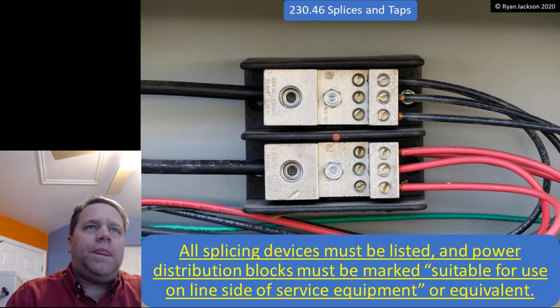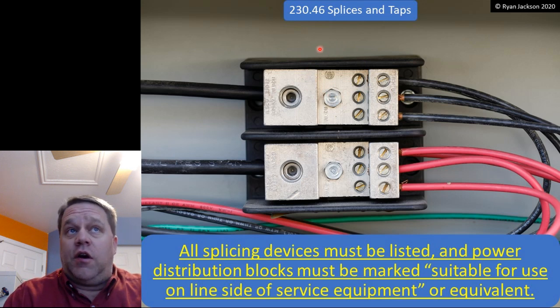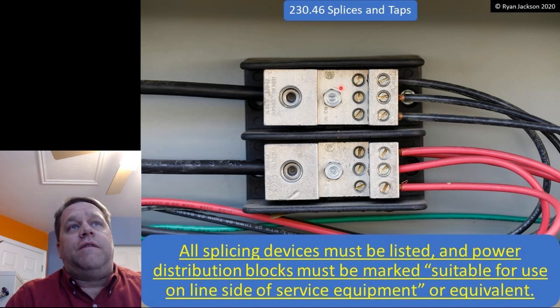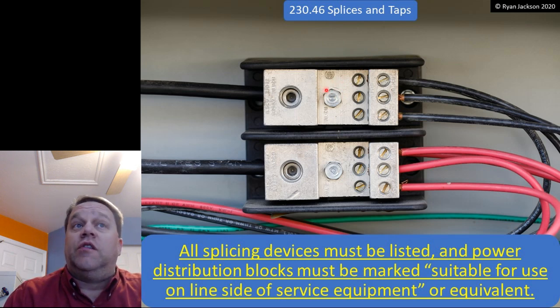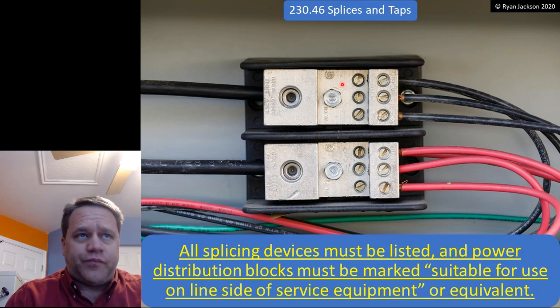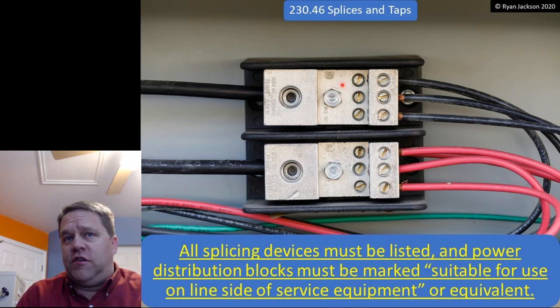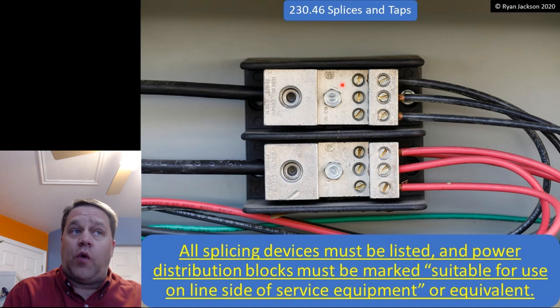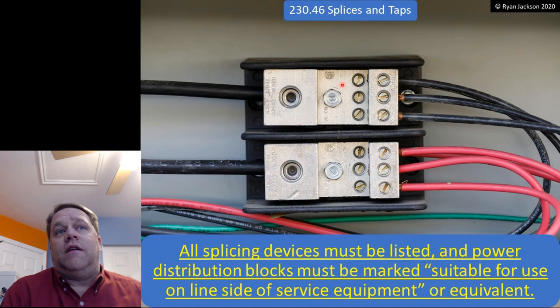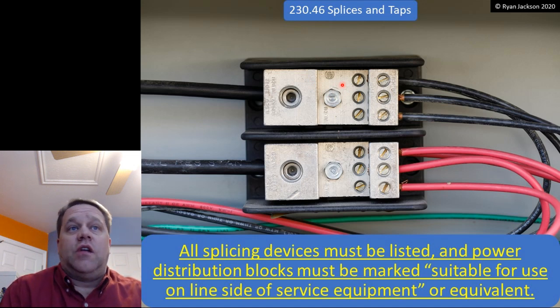So it might be a little bit hard to see, but right here is a mark from CSA, Canadian Standards Association, and that is a listing mark. It's only for Canada. But if there is a little U next to it, like United States, then that would say that this is suitable for use in the United States as well. So splicing devices now have to be listed. That was not required before. A lot of people think that everything has to be listed, and that's not the case.